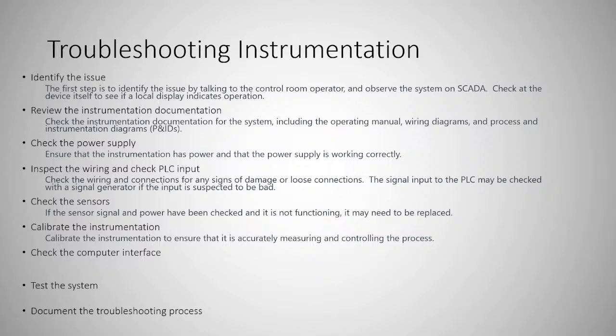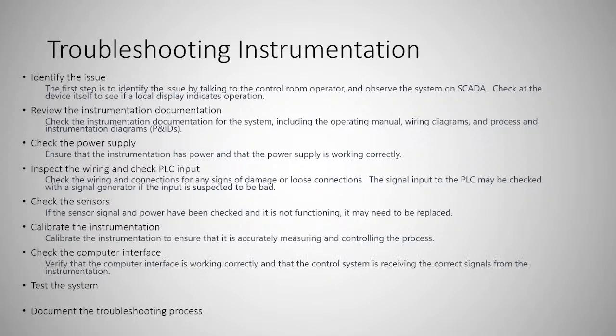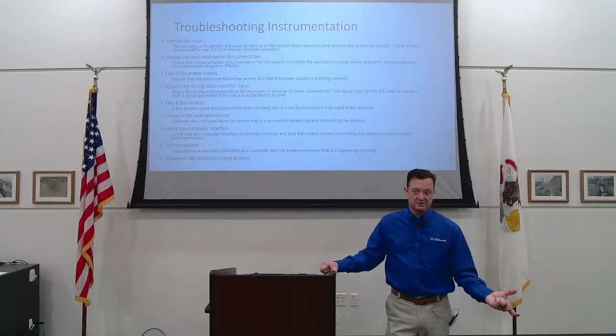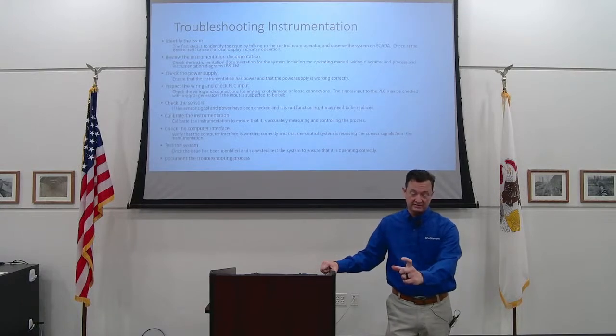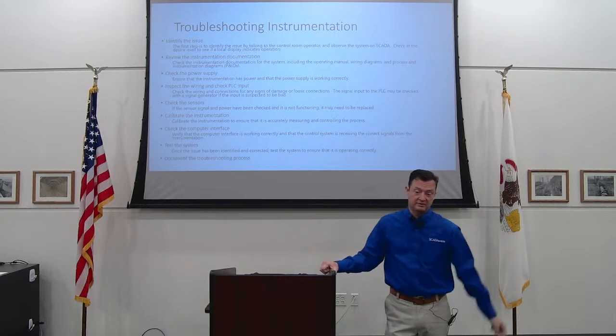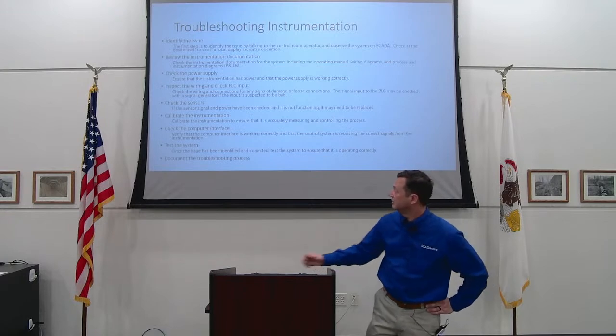And verify that the computer interface is working correctly and that the PLC is reading the signal. And then if you get it back online, obviously, it's really critical that you test it, right? Especially with instrumentation, if it's reading on the system again, make sure it matches what you're actually seeing in the field. If you have a display on the device, such as a level transmitter, make sure it's reading the same on SCADA as it is on the device itself.